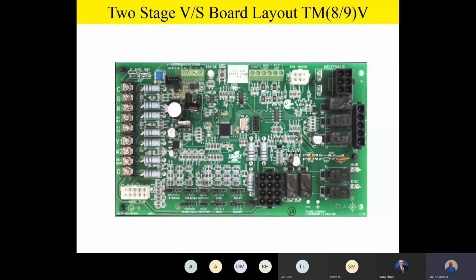This board is communicating capable. We'll talk about that in a minute or two. But let's take a look at those low voltage terminals on the left-hand side, because they are a little bit different than the previous boards we talked about. So starting out, C on the low voltage terminal strip to the left is 24 volt common. That's very straightforward. G is our fan call. R is 24 volt hot, just like before.